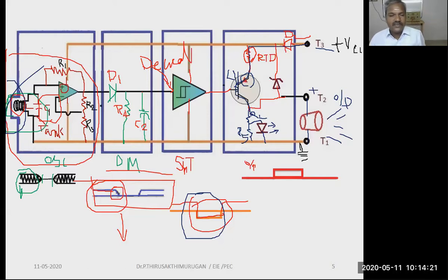Same concept. If the object is away, you see this is decreasing. The moment the object is moving away from the sensor head, the oscillation starts again. It reaches the resonance frequency. So when the demodulator output increases, the increasing voltage is applied to the Schmitt trigger. So due to that increasing output, the Schmitt trigger goes high. Okay, the Schmitt trigger goes high.